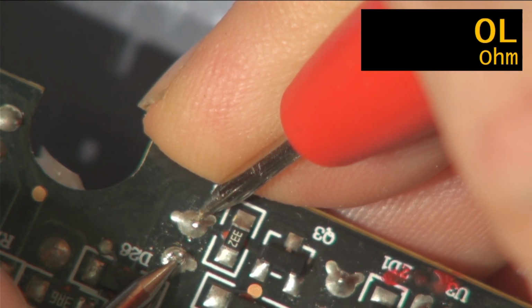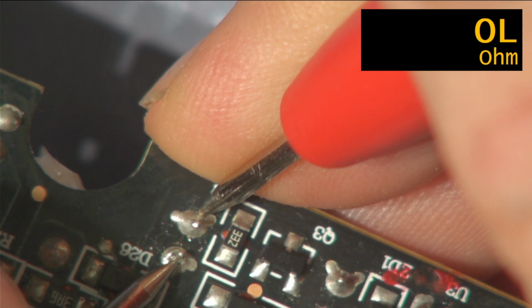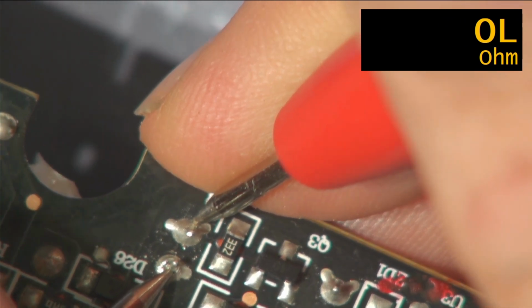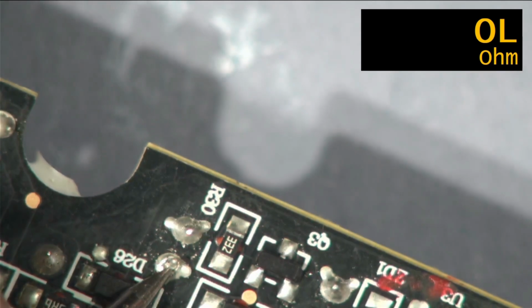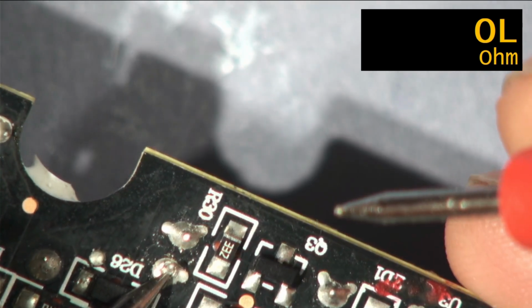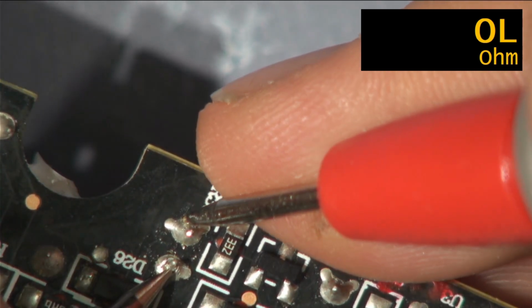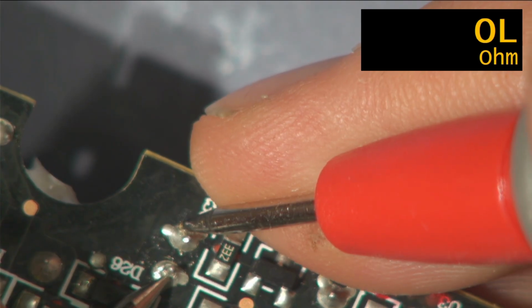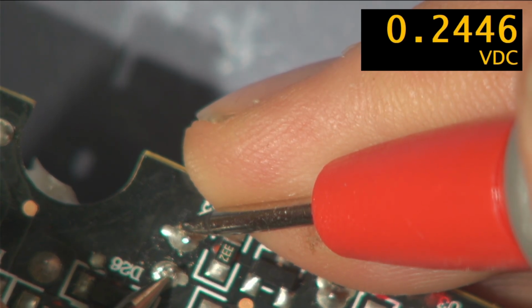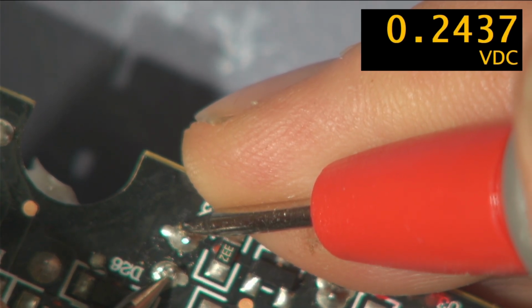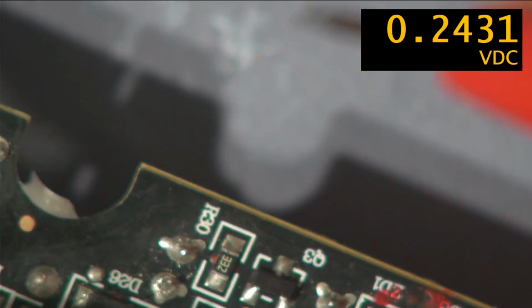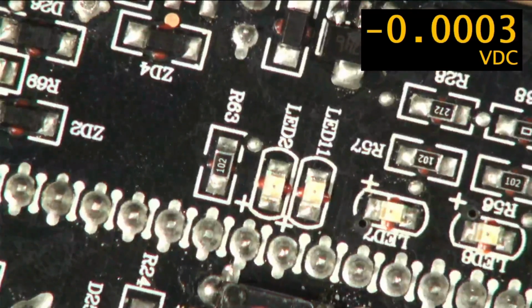So you can see the capacitors are charging and it's open circuit, so there is no short on the secondary side. If I go back and check the actual DC voltage there, we'll have charged it to... there you go, 0.2437 volts. So I don't think there's a short on the other side, but we've definitely got a short on this side.